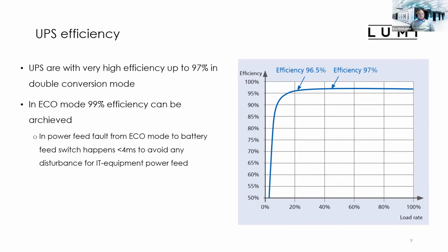In eco mode, these UPSs can achieve 99% efficiency, and in a power feed failure in this eco mode, the UPS can turn to battery mode in less than 4 milliseconds to avoid any disturbance to the IT equipment power feed. But this is something that we haven't implemented, so we are happy with the efficiency in the double conversion mode, which is up to 97% in our case. There is not so much difference anymore between 97 and 99% to go to eco mode.